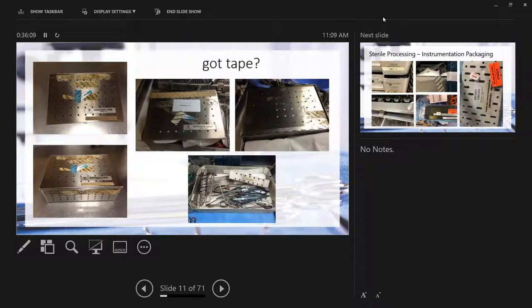Here, it's not so much the pan, but the pan inside holding the smaller items that I put a label on. And you know where those labels come from? The little machines you can buy from Staples—you plug it in and it peels out. That's not rated for time-temperature sterilization, and it should never be there. Second, steam is water, and water can't penetrate the glue or stickiness of the tape. So this is technically worse than or equal to bioburden, but everybody in the country I go to is doing a very similar thing.